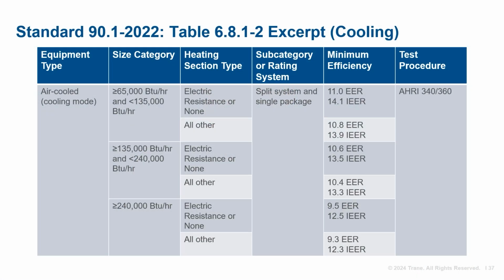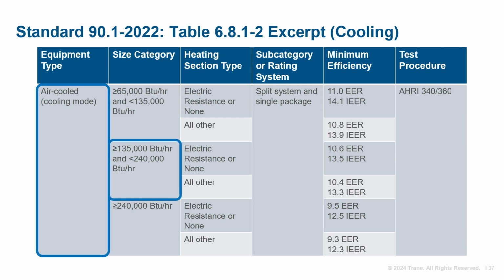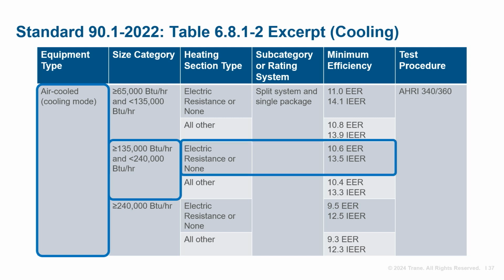Now, to account for this, ASHRAE's energy standard, 90.1, sometimes uses 2 ambient temperatures in the minimum efficiency rating. Here's an excerpt from Standard 90.1 2022 for air-cooled packaged unitary equipment. Let's consider an example 12.5-ton heat pump rooftop with an auxiliary electric heater. First, cooling efficiency. The unit is 150,000 BTUs per hour, so it fits into this capacity range. And since it has an auxiliary electric heater, the minimum efficiency is 10.6 EER at full load and 13.5 IEER at part load.